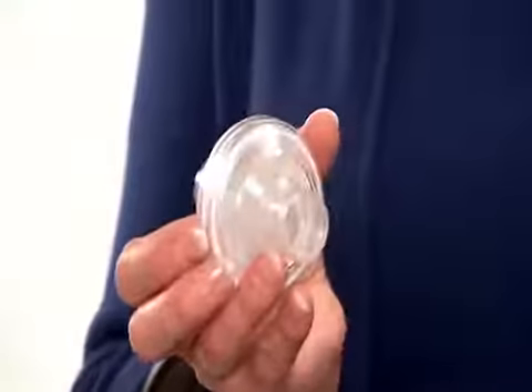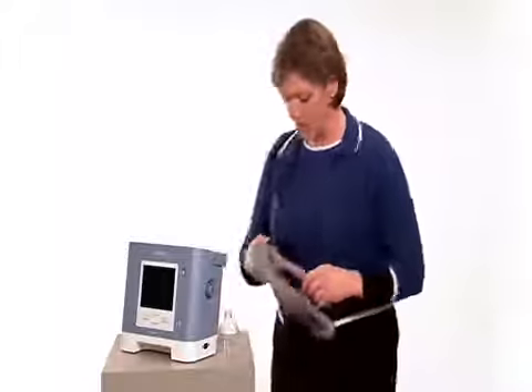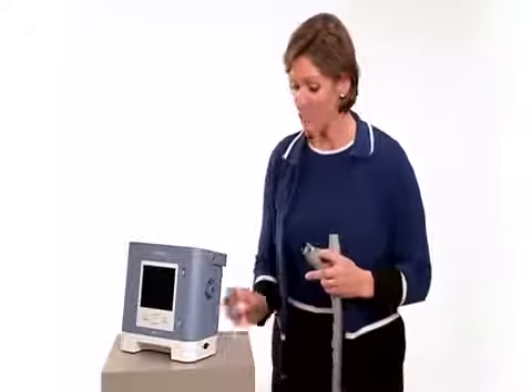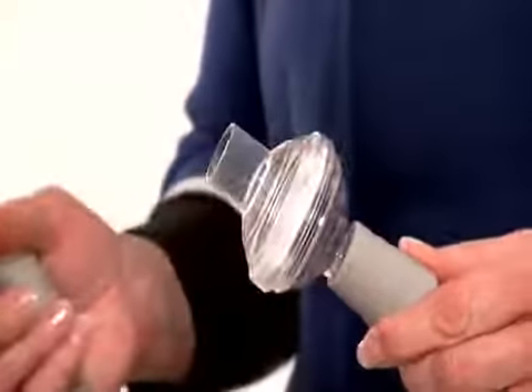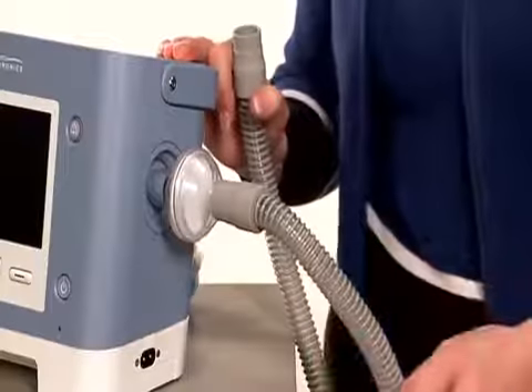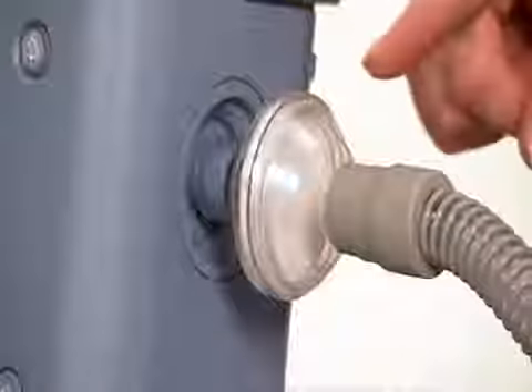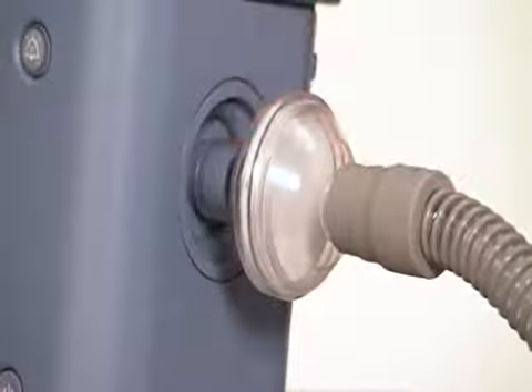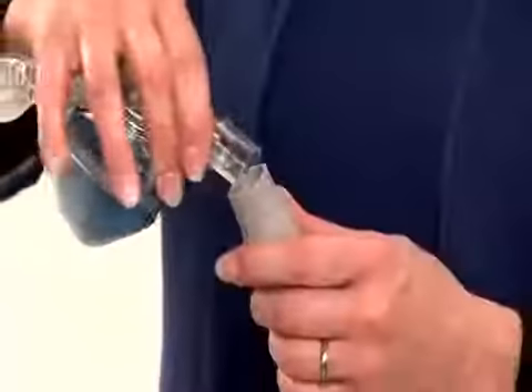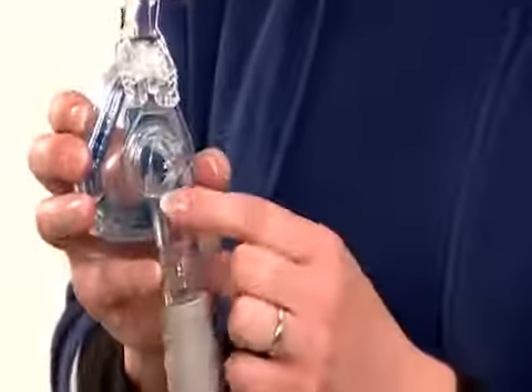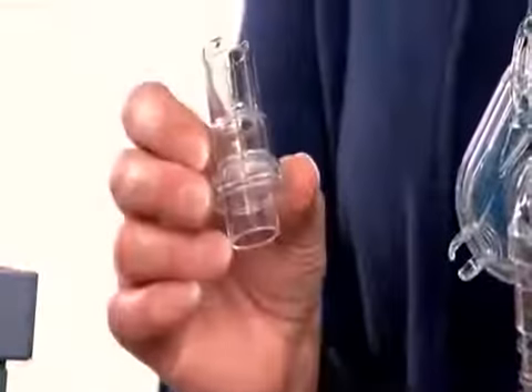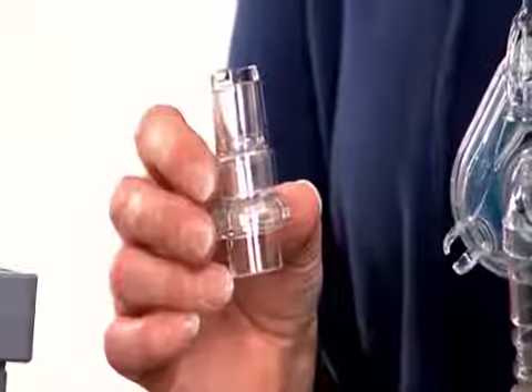The ventilator is designed to work with either a passive exhalation port or an active exhalation valve. An optional bacteria filter can be used with either type of valve. To set a passive circuit up, connect one end of the flexible tubing to the outlet of the optional bacteria filter. Insert the bacteria filter inlet to the breathing circuit connector on the side of the ventilator. If you aren't using the optional bacteria filter, attach the tubing directly to the breathing circuit connector. Connect the other end of the tubing to a mask with a built-in exhalation port. If connecting to a trach tube or a mask that does not have a built-in exhalation port, connect a Whisper Swivel 2 exhalation port to the end of the tubing. If you're using a passive system, your breathing circuit is complete.